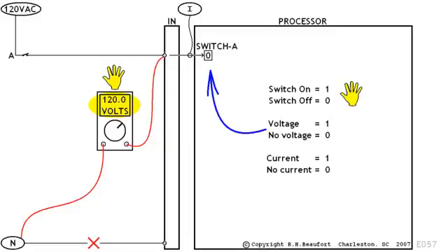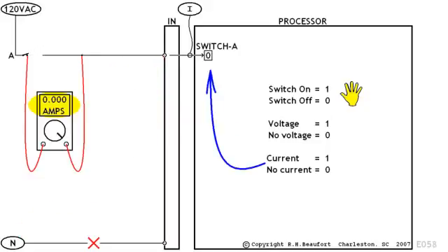That's a mistake. Using a milliamp meter for testing is harder to do since it has to be connected in series with the input circuit, but the test is usually more conclusive. Notice that no current on the meter explains the 0 status of the bit. We'll cover all of these ideas in more detail when you go through the class.